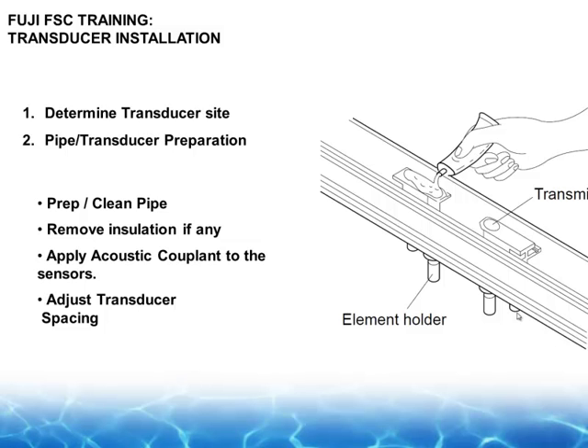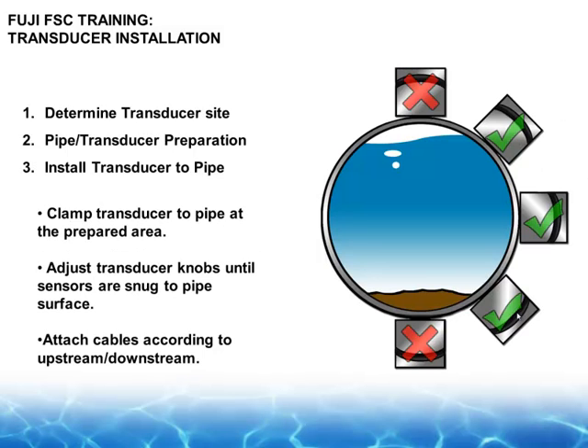So we butter up our transducer just like toothpaste on a toothbrush. Put it on the pipe, adjust your spacing. You can hand hold it or you can strap it to the pipe. Locations on the pipe: the top of the pipe can have air, and the bottom of the pipe can have solid. So anything on the side, anything at 9 or 3 o'clock, is usually the best installation point.